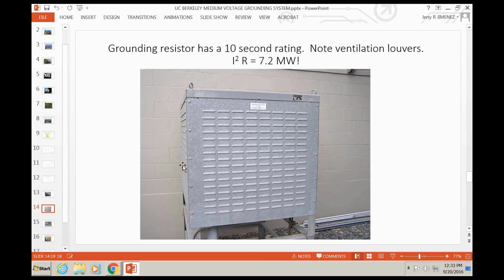Next picture, a little close-up of the grounding resistor. Note the ventilation louvers here. I never really realized how much power has to get dissipated until I got ready to do this presentation. It's got a 10-second rating, but the I squared R, that's 1,000 amps squared times 7.2 ohms, is 7.2 megawatts. A lot of juice has to get dissipated in this grounding resistor. That's why it's only got a 10-second rating.